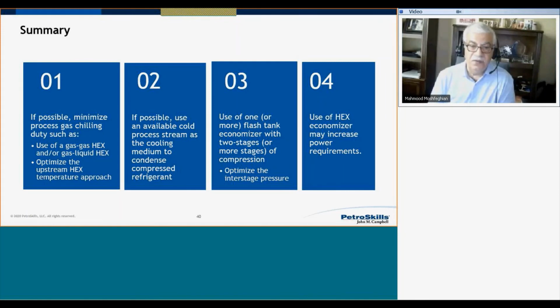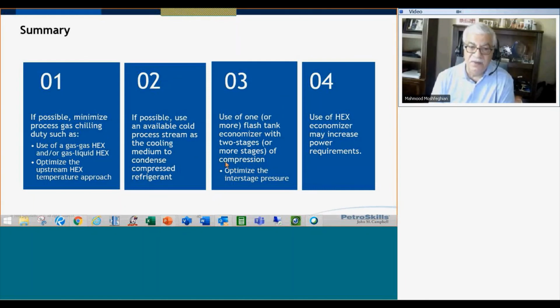So when you size the refrigeration system, don't look at the chiller itself. Have an eye on the upstream gas or gas-liquid heat exchanger to lower the chiller duty right at the start. Item 2, if possible, use an available cold process stream as cooling medium to condense compressed refrigerant, as we did. You are going to receive a copy of this PDF, this presentation.